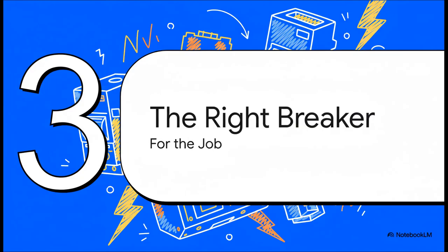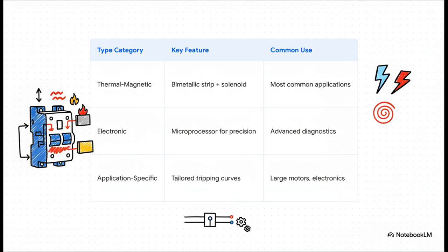Now, not all electrical loads are created equal, right? A giant motor has way different needs than, say, a server room, and that means MCCBs can't be a one-size-fits-all solution. You've got to pick the right breaker for the job. Okay, so your standard workhorse is the thermomagnetic type we've just been talking about. But for more advanced stuff, you have electronic trip units. These use a little microprocessor for incredible precision, and you can actually fine-tune the protection settings. And then you get application-specific types, with tripping curves tailored for really unique loads, like a Type D breaker that can handle the massive startup current of a big motor without tripping by mistake.